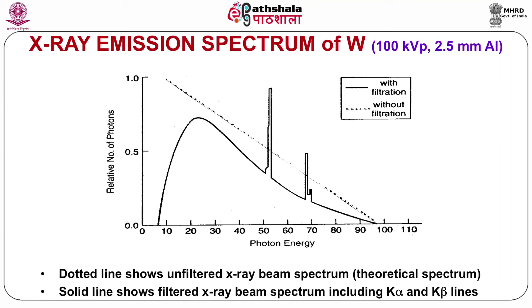When energetic electrons are allowed to strike a high Z target for production of X-rays, they are slowed down and are stopped in the target within a range of a few micrometers. The depth of penetration of electrons in the target material depends on the accelerating potential and target material. Thus, X-rays are not generated at the surface of the target but within the target, resulting in an attenuation of the X-ray beam. The attenuation of X-ray is called filtration, and as it is happening in the material in which it is produced, the phenomenon is called self-filtration. The self-filtration appears most prominent at the low energy end of the spectrum, that is, the left hand side of the curve.